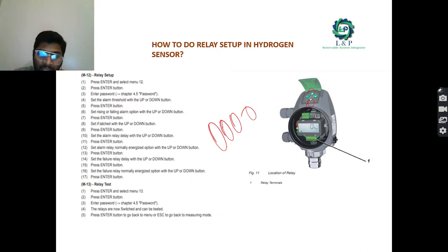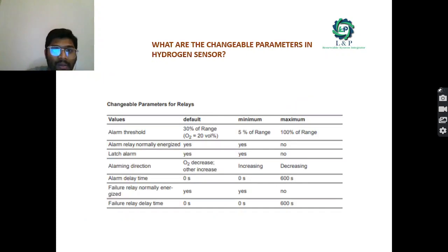Press the enter button, get into menu 13, press enter, and you have a password value 0000. Once it is done, the relays are now switched on and can be tested. Press the enter button and go back. If you want to go back, use the escape button for the measuring modes.